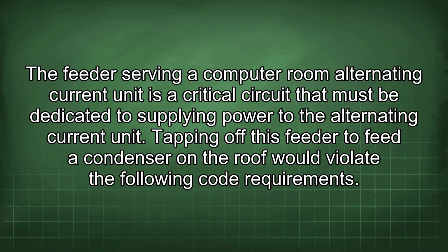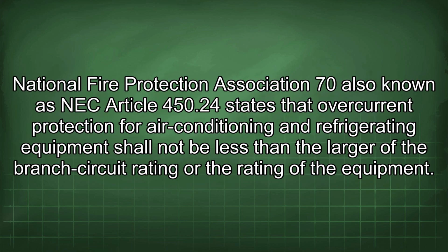The feeder serving a computer room alternating current unit is a critical circuit that must be dedicated to supplying power to the alternating current unit. Tapping off this feeder to feed a condenser on the roof would violate the following code requirements.